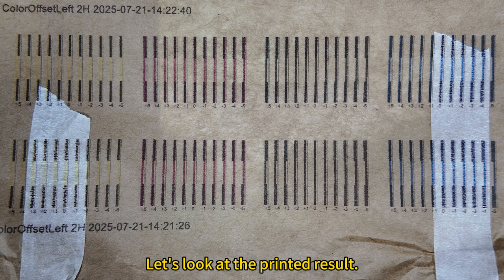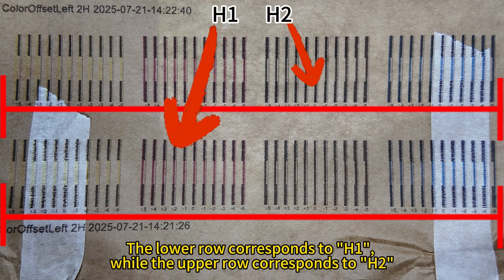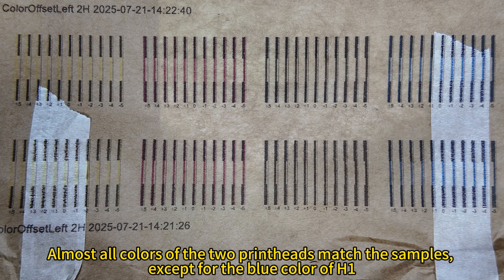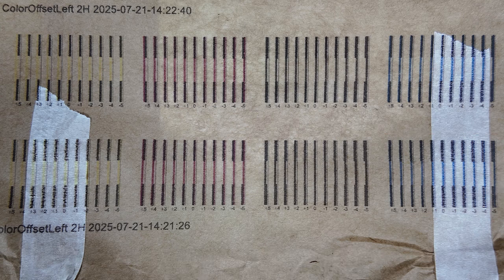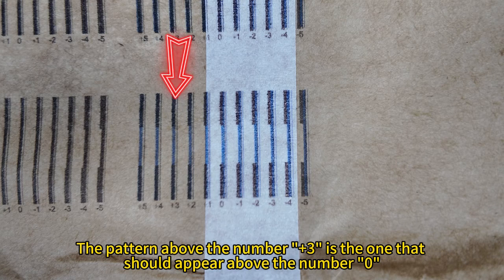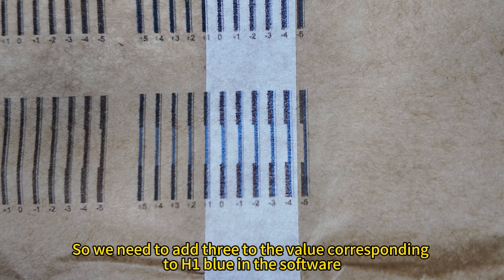Let's look at the printed results. The lower row corresponds to H1, while the upper row corresponds to H2. Almost all colors of the two printheads match the samples, except for the blue color of H1. The pattern above the number +3 is the one that should appear above the number 0. So we need to add 3 to the value corresponding to H1 blue in the software.